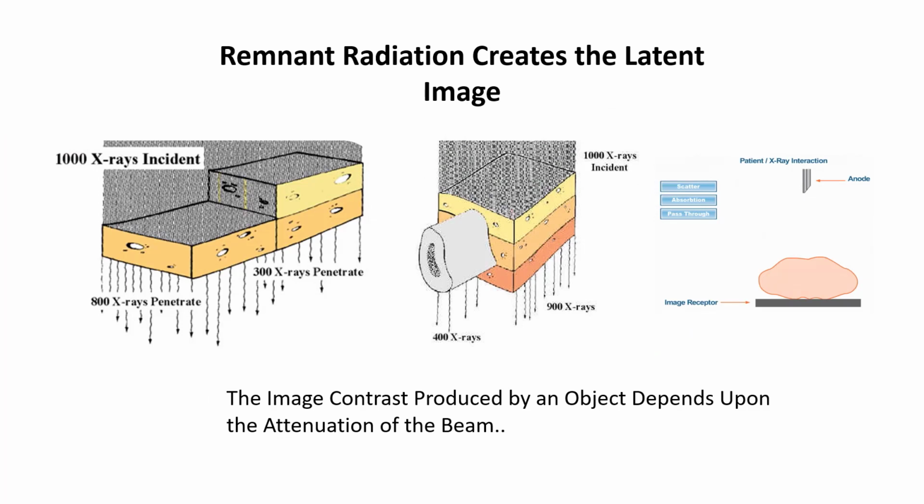Attenuation of X-rays in solids takes place by different mechanisms, some due to absorption, others due to the scattering of the beam. Differential absorption is based upon both the thickness and composition of the object being X-rayed. The remnant radiation forms a latent image. Absorption characteristics of materials are important in the development of contrast to visualize the image. In formulating exposure techniques, differential absorption is a primary factor.